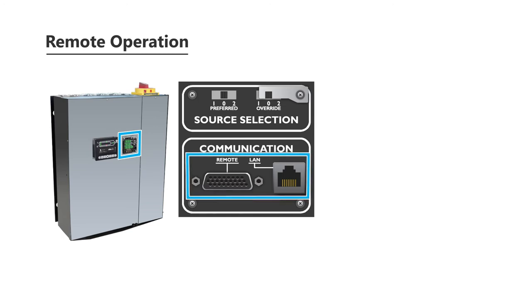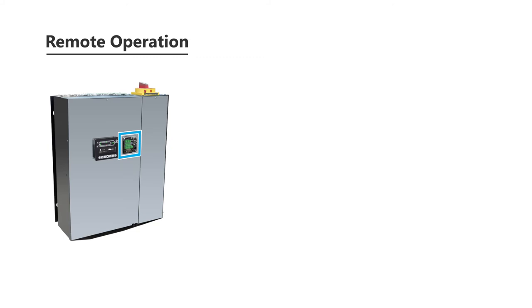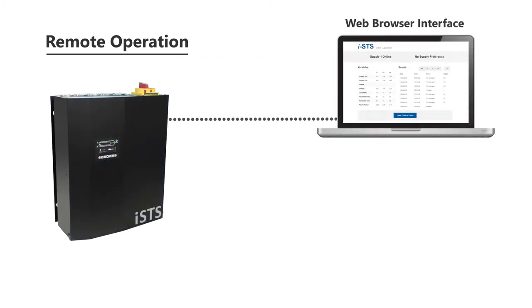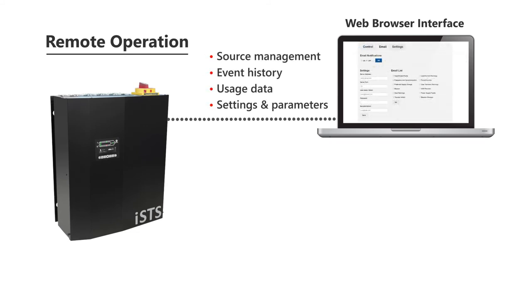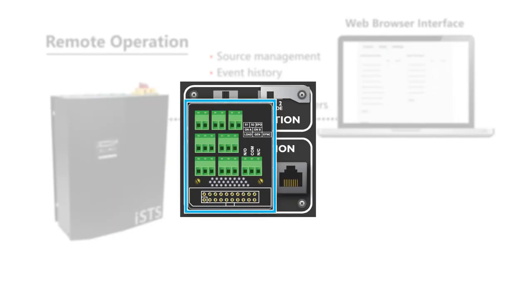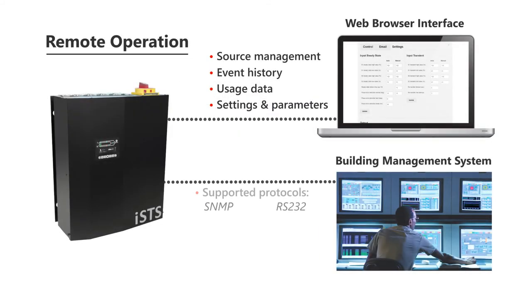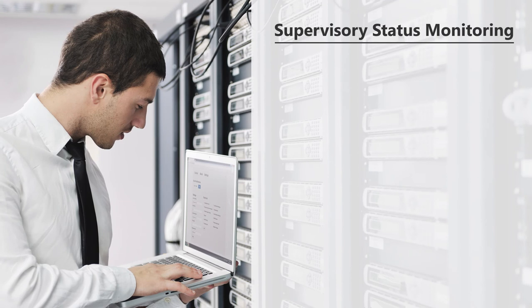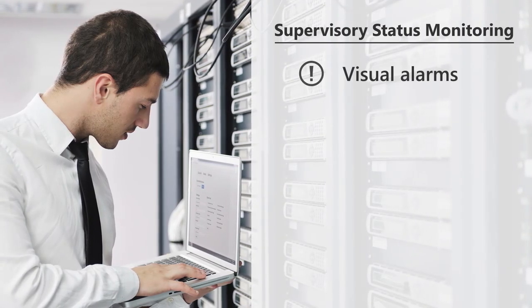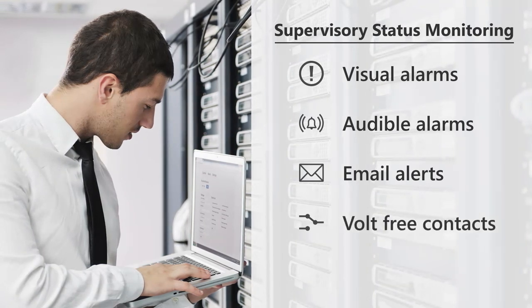Terminals for remote connectivity are located behind the front panel. Connect to the STS via Ethernet and use the web browser interface to remotely access source management, event history, usage data, settings, and parameters. Easy-to-connect terminals enable integration into building management systems, compatible with common industry communication protocols without the need for proprietary software. The user is kept informed of the STS state with visual and audible alarms, email alerts, volt-free contacts, and LAN.